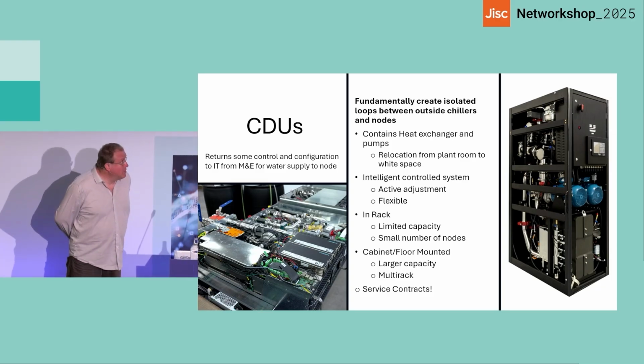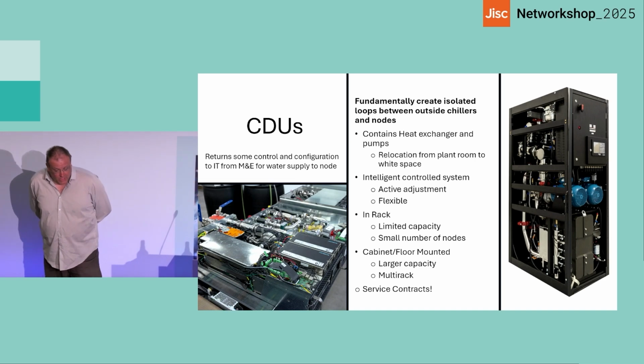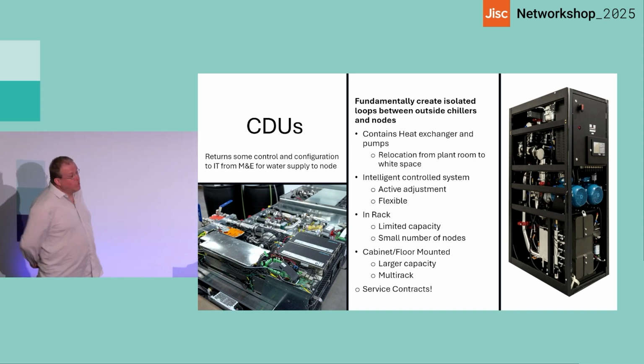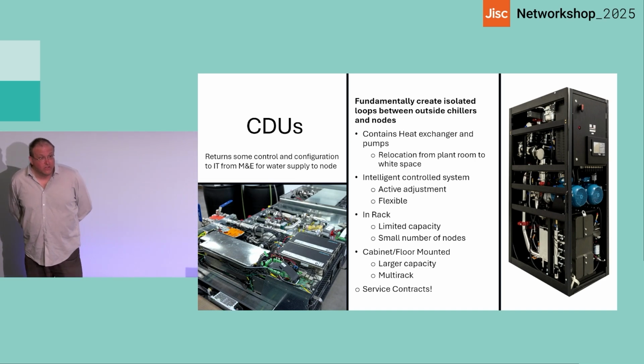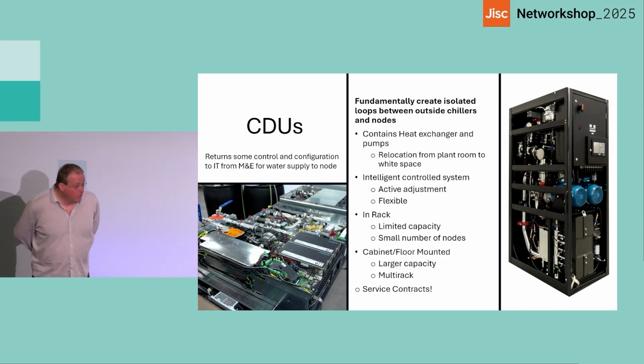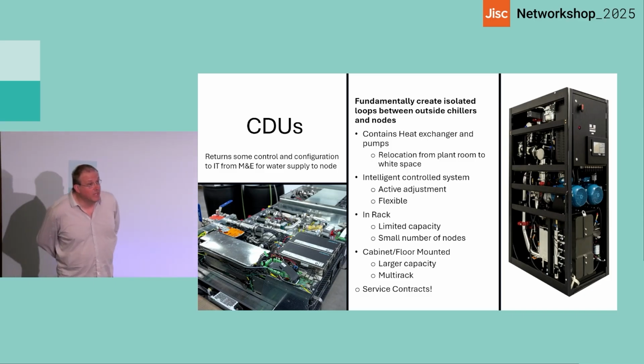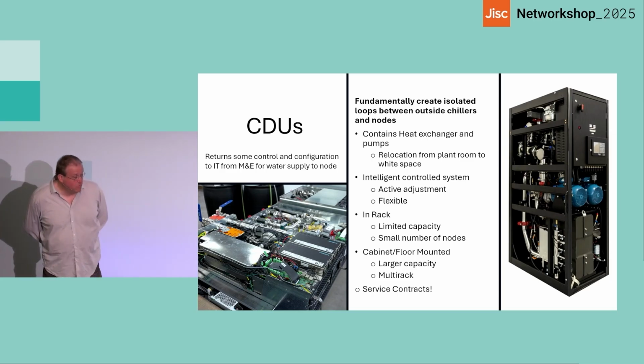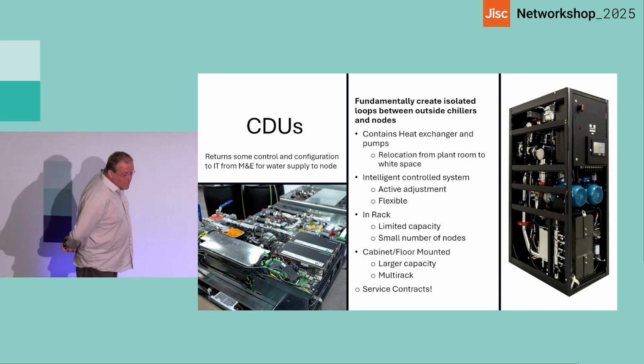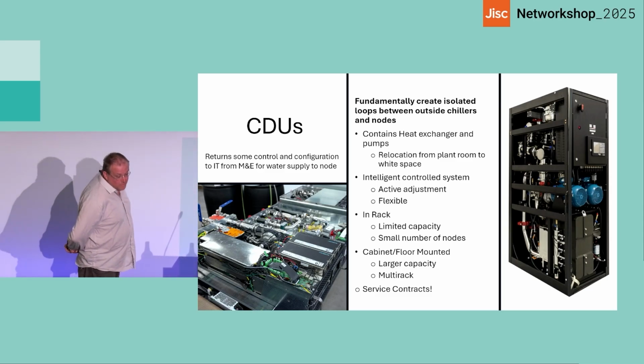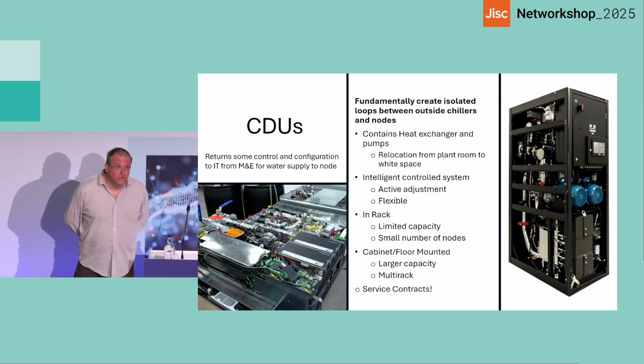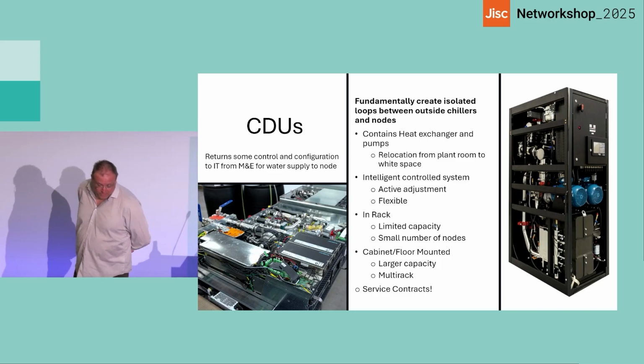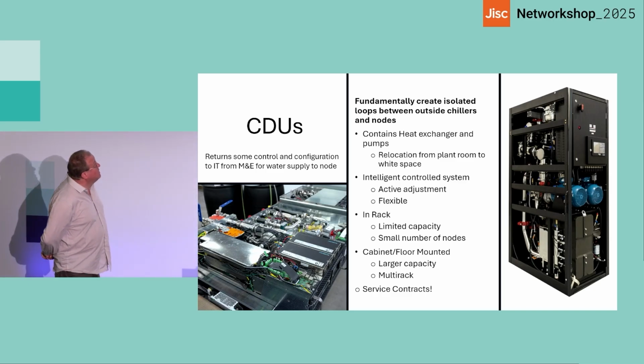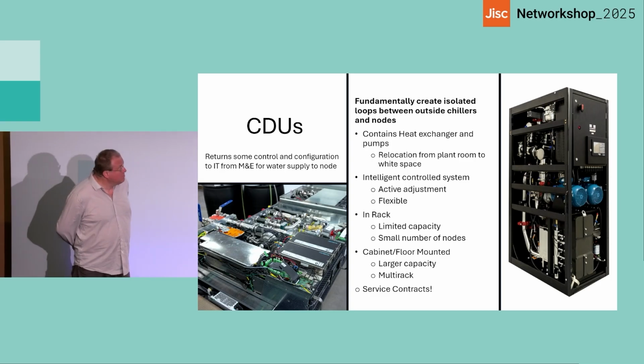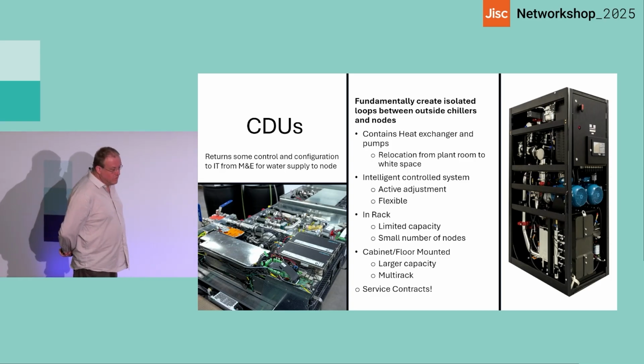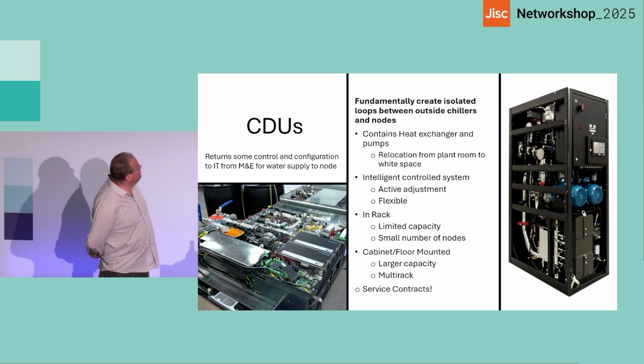I've got 2 examples of CDUs here. The one on the right as you're looking at it is a large 600 odd kilowatt unit designed for multiple racks. The one on the left is an in-rack unit designed for a couple of 100 kilowatts, just put it in the rack. They're all fundamentally the same. They have slightly different resiliencies, but generally you'll find they've got heat exchangers and pumps in them. So you've relocated all this equipment from the plant room into your IT space where you have control. They're intelligently controlled systems, designed to be actively adjusted and very flexible, so you can tweak how much equipment goes into them and they'll adjust and you can configure them.